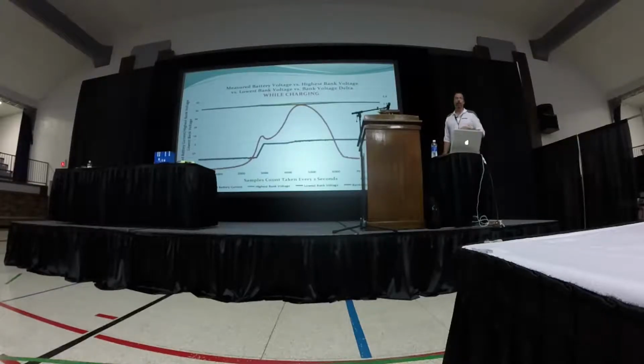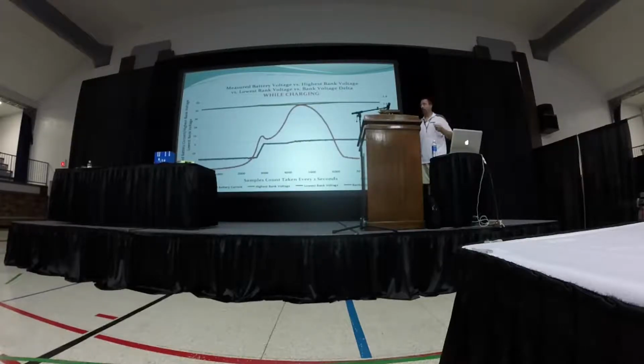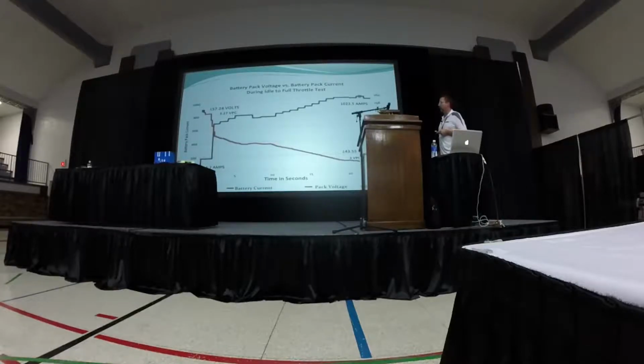And that's what we're seeing: during charge and during a drive cycle, the differential between the banks is really low. That's important, because if that delta voltage gets too high, we can detect a problem in a bank. Whether we're charging or discharging, going along at 300 amps, we can monitor our high and low banks right here. If a cell goes sideways in one bank, then that delta is going to go way up. And we can detect that, throw a fault, display it, and alert you as to what's going on.